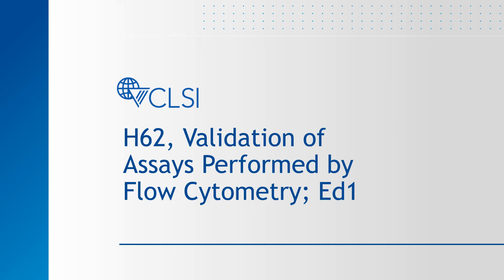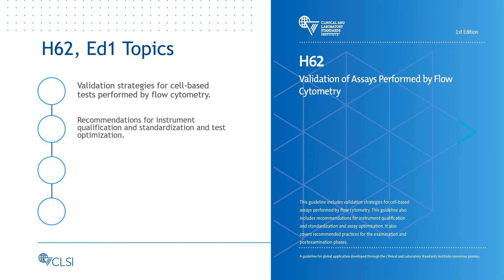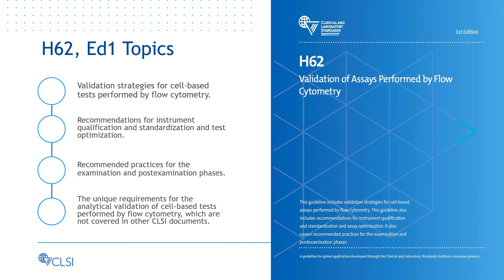Welcome to this overview of CLSI's H-62, Validation of Assays Performed by Flow Cytometry, First Edition. CLSI's H-62 includes validation strategies for cell-based tests performed by flow cytometry, recommendations for instrument qualification and standardization, test optimization, and recommended practices for the examination and post-examination phases. It focuses on the unique requirements for the analytical validation of cell-based tests performed by flow cytometry, which are not covered in other CLSI documents.